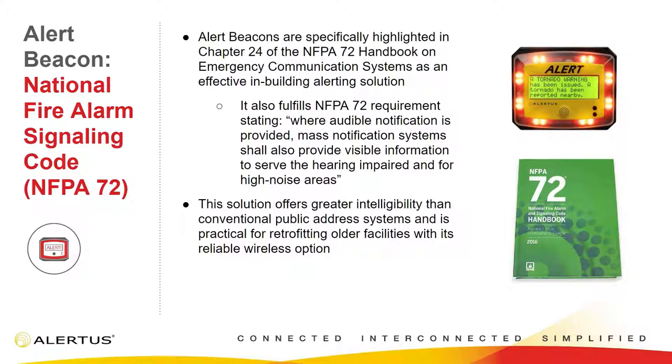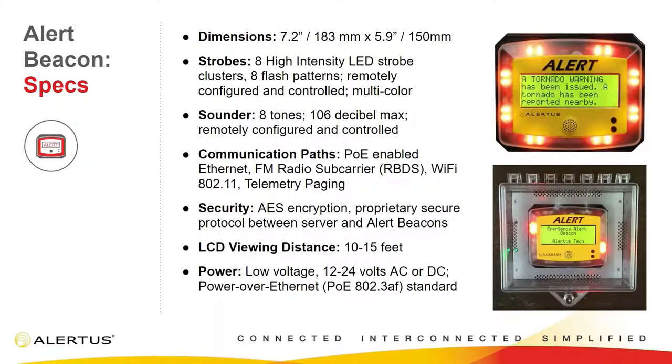This also falls in coordination with a lot of codes. We're actually in the NFPA 72 handbook, right next to the section stating that where audible notification is provided, a mass notification system shall also provide visual information to serve the hearing impaired and for high noise areas. You can't necessarily rely solely on audible notification — if people are hard of hearing or in a noisy environment, they might not hear it. The flashing lights are really important for capturing attention. Both with ADA compliance and NFPA 72, the Alert Beacon is a great option.